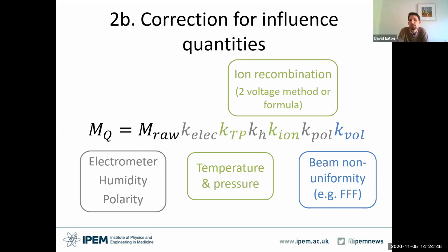We also need to be careful about the beam non-uniformity correction for our FFF beams. So if we have a relatively large chamber in a non-uniform beam, then there may be some correction, even if we have it on central axis. And there's some discussion of that in the report as well. The other factors: many centres will calibrate their electrometer and chamber together. So potentially you might have an electrometer calibration factor for your secondary standard, but not for your field chamber. But you will need to consider these factors, the same with humidity and polarity. They may well be unity, but certainly when you're setting up your initial values, you need to be aware of them and be sure that they are unity.